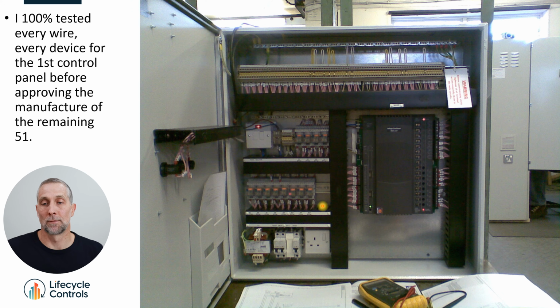This control panel is fully loaded for 52 different air handling units. So we didn't have different control panels for different AHUs. There's just 52 of them exactly the same. If an installer went into a plant room and there were 4 AHUs there, walk downstairs to the storeroom, grab 4 AHU panels, screw them onto the AHUs, don't care which panel goes where, they're exactly the same.